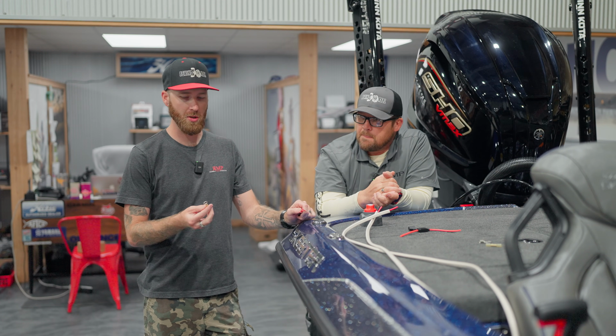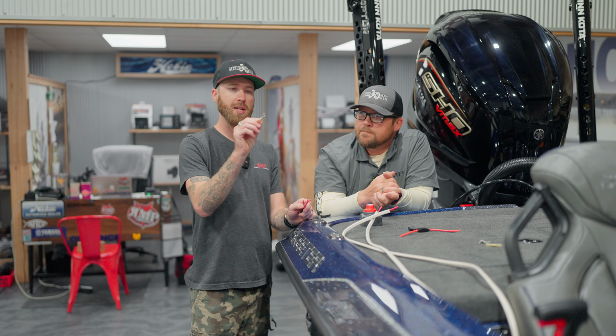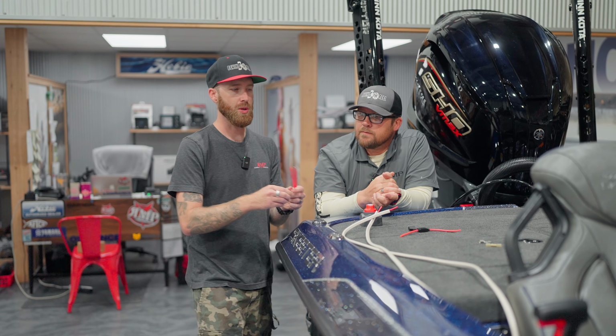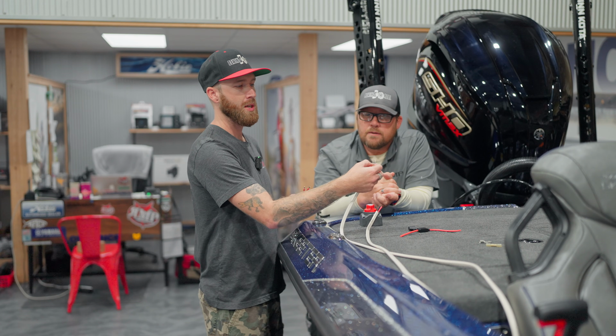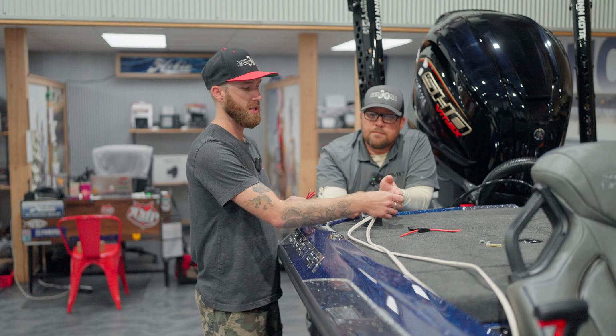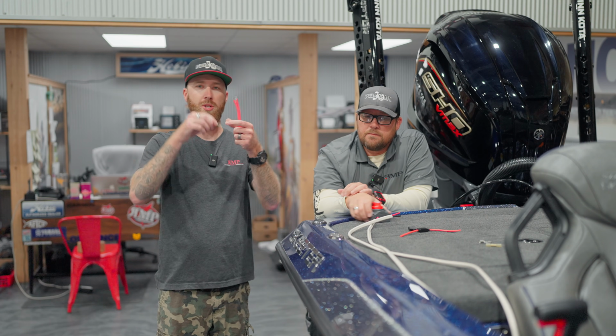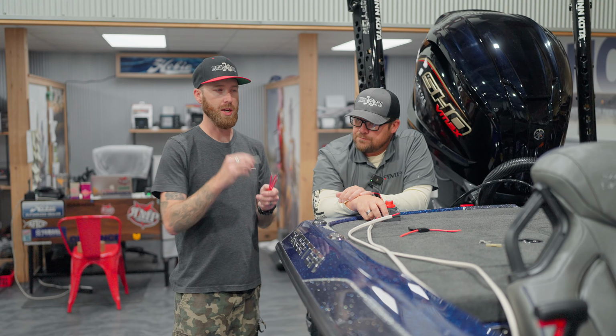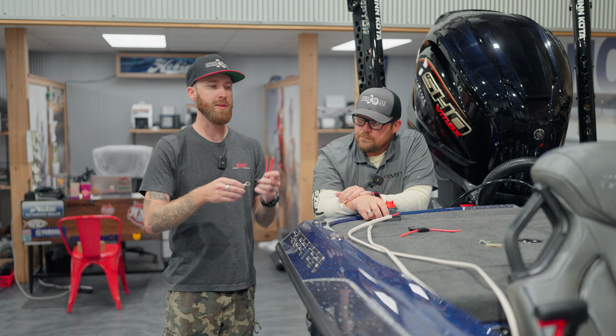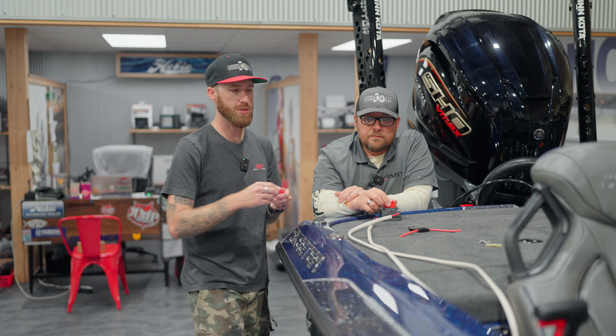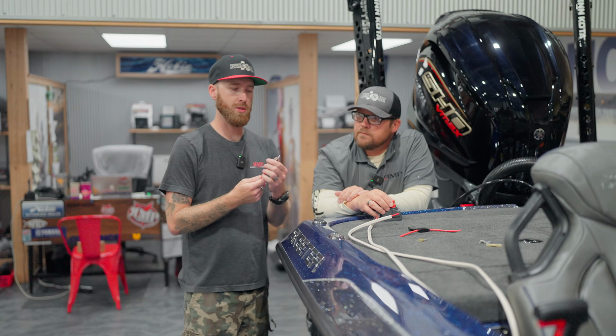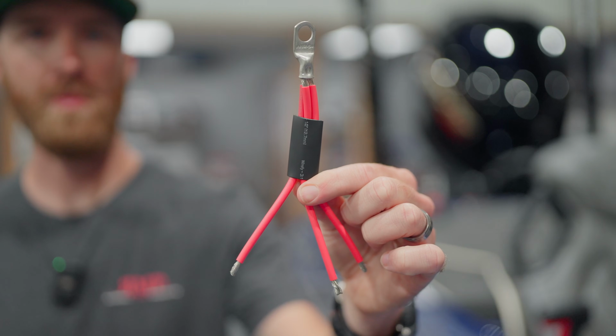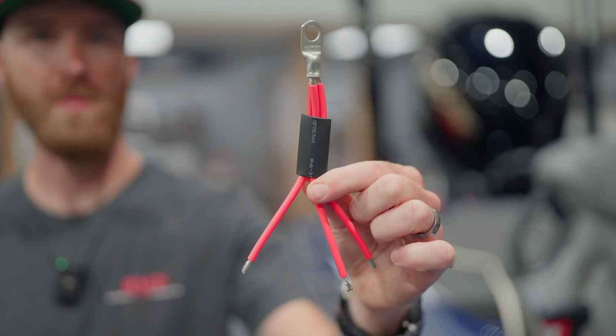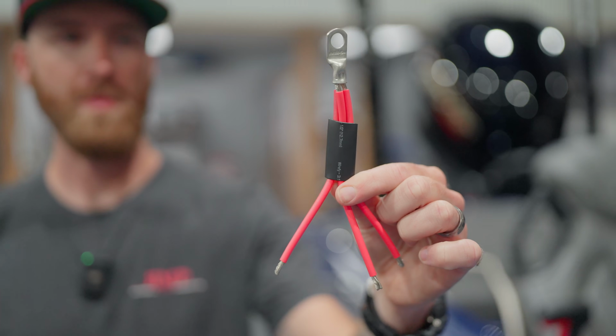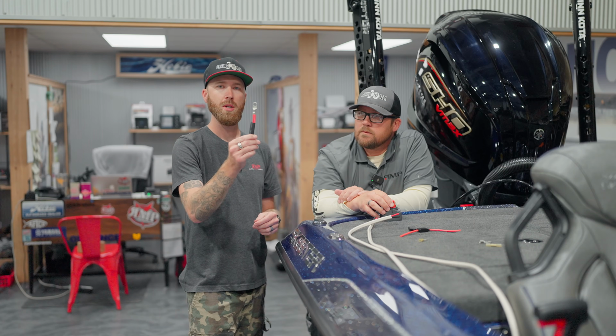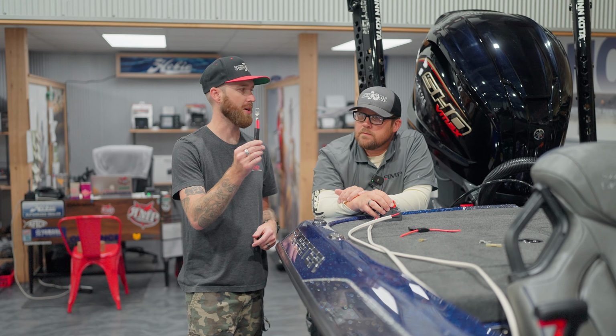4 units and a live scope or an active target or a mega live, something like that. So this is like your typical 10 gauge ring terminal. If you used these individually to connect to the Perko switch, you'd have a whole bunch of them stacked up on top of each other, and sometimes that's fine, but sometimes you actually run out of room there. So what we do a lot is use these bigger butt connectors, and we'll connect 3 different 10 gauge wires all into one ring terminal.